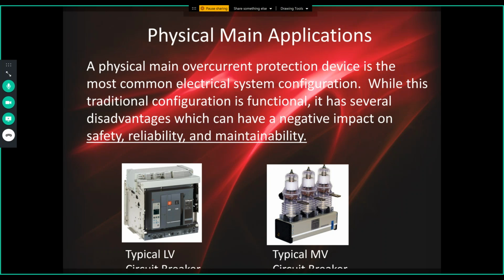And of course, the biggest safety drawback here is the line side of that secondary main breaker. Without a secondary virtual main, if you just have a physical main, as long as your transformer is greater than 125 kVA, which is not very big, you're going to be PPE category dangerous. There will be more than 40 calories per centimeter squared at the 18-inch working distance. And I've shown here a typical low voltage breaker on the left and a typical medium voltage vacuum breaker on the right.